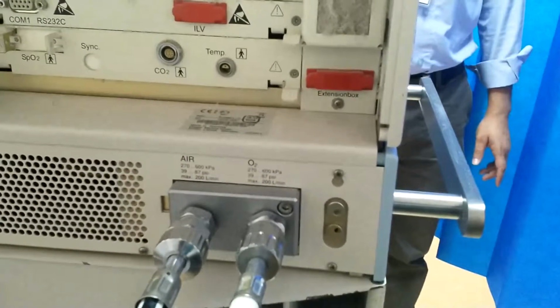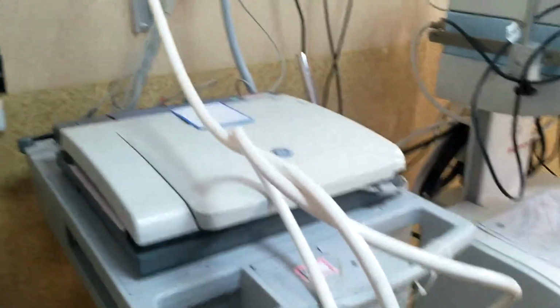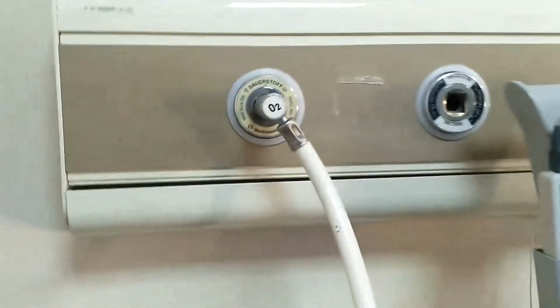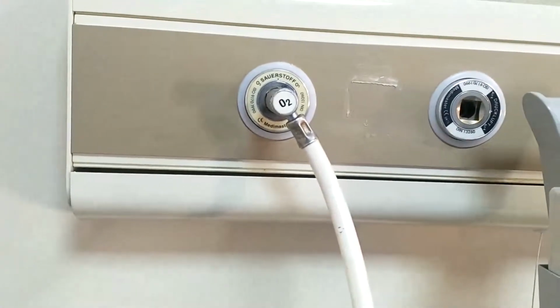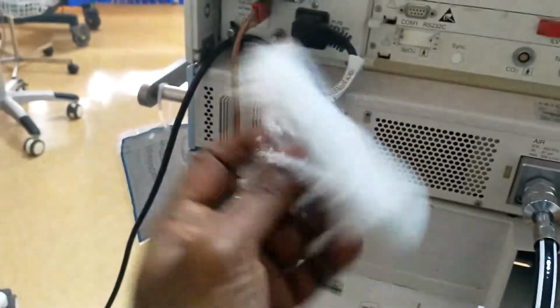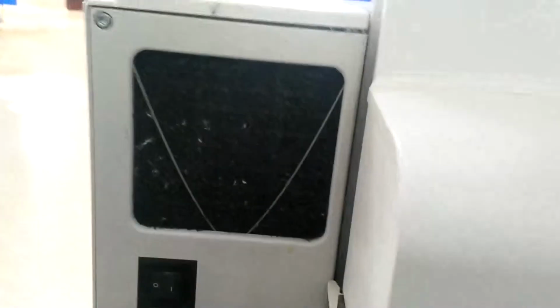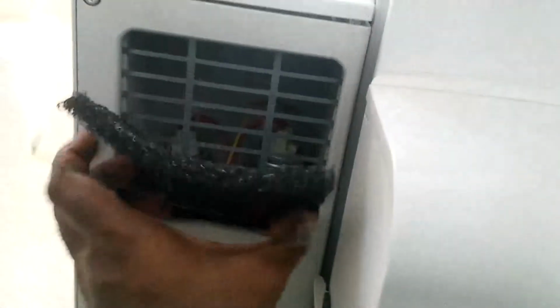But the oxygen pressure is being provided by the central gas supply. White color tube is oxygen and black and white is air. Along with this, we would have to clean the filters. You can see that it is dirty, so we would have to pull out and clean the filter once in a while. And even in the compressor, the air inlet filter, we would have to take it out and clean it once in a while. So this is also our job.